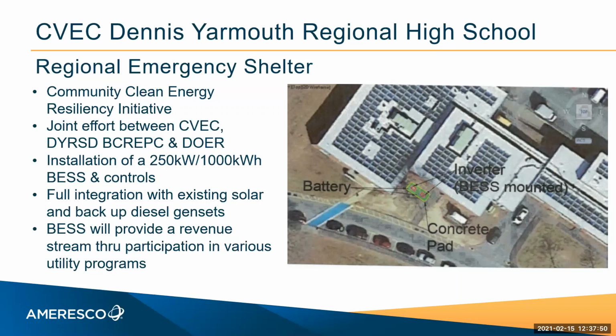Further, the program has some flexibility. There's actually a third-party aggregator that aggregates the output of multiple assets and applies those to the ISO. But my understanding is that the first priority is always to serve the shelter if there's a grid outage.